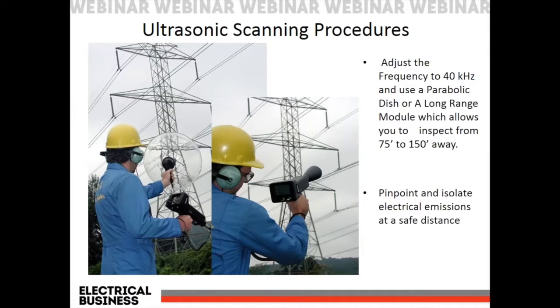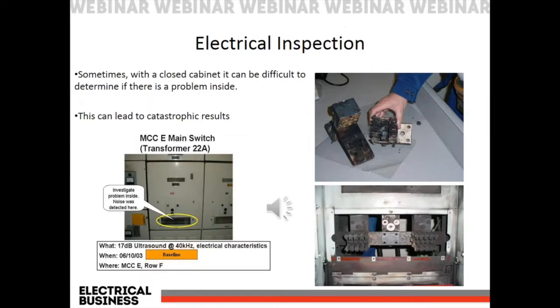So that's one way. There's another way, of course, where we can get into longer ranges. One of the big questions I get is, how far can you actually go, Sean? And I said, our equipment can reach up to about 150 feet away using the parabolic dish that you see on the left there, to a 5-degree radius. The one to the right is our long-range module, where we can go up to about 100 feet away with a 10-degree radius, and that's commonly used in a lot of the substations that we go out to. But when we're dealing with the high towers, like we are on the left, the parabolic dish becomes a very powerful tool to pinpoint. So we can literally pinpoint which insulator is causing the problem, and then we can say that insulator is either tracking, has arcing, or maybe corona there, and that's the key. We're able to diagnose these things, and that's the big benefit, right?